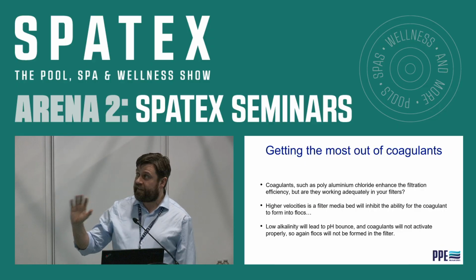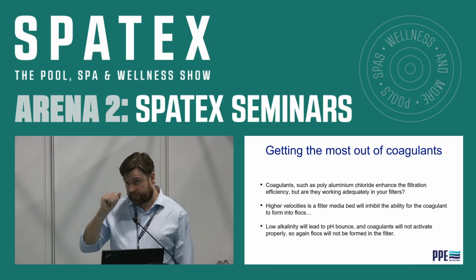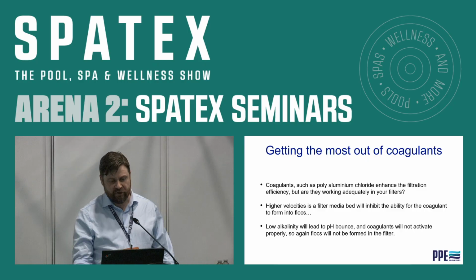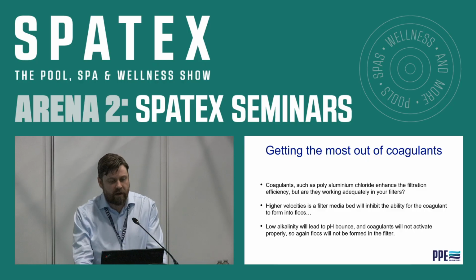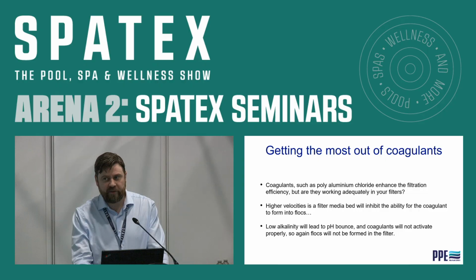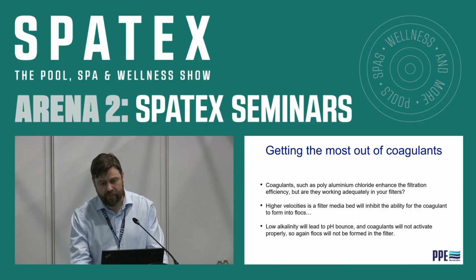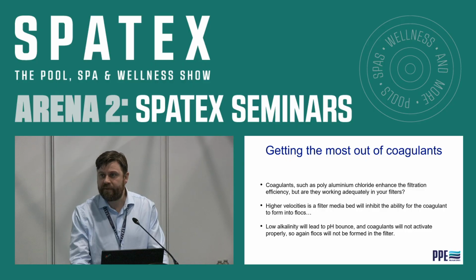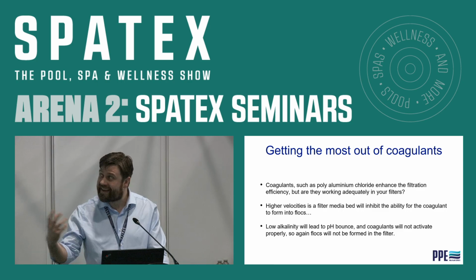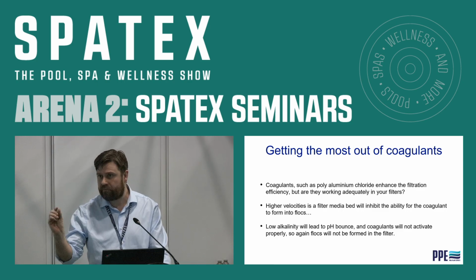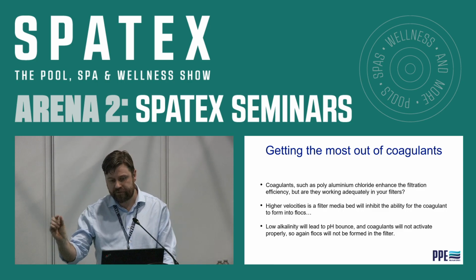We've also got to think about coagulation. With coagulation, we're trying to enhance the removal of dissolved or colloidal matter, including even biological matter like cryptosporidium, within the filtration media. Normally, most filters, when they're in good condition, will be taking out about 8 to 10 micron diameter of pollutants.